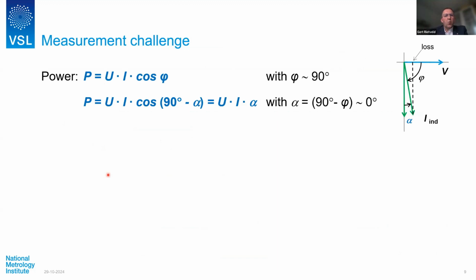And then what does it relate to in the measurement challenge? Again, I'm referring to the formula already shown for sinusoidal waves by Ilya. Power is current times voltage times cosine phi. And we are now not energy metering, not billing, but we are measuring losses. And here I indicated the schematic. For an ideal inductor or power transformer, the current would be fully perpendicular to the voltage, 90 degrees. But in reality, there are some losses, and that causes the phase angle to slightly deviate from 90 degrees.